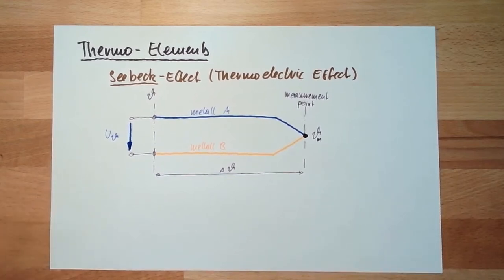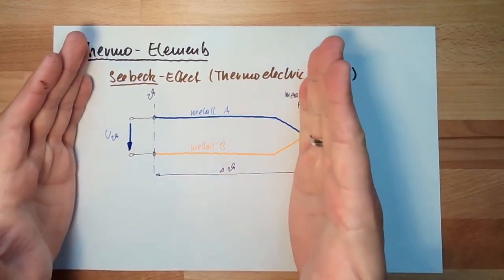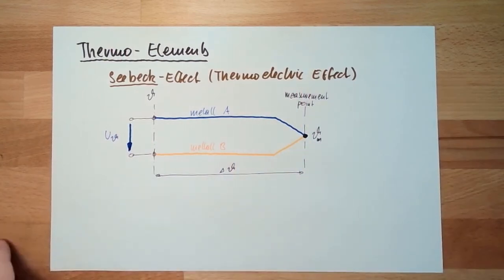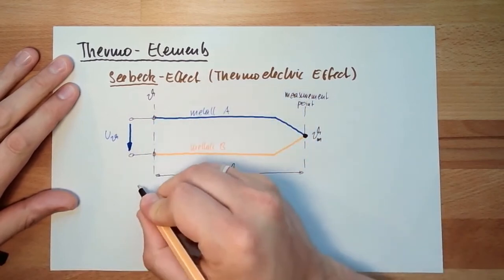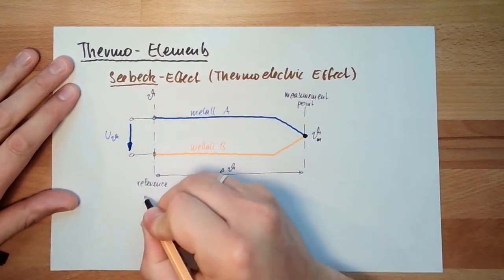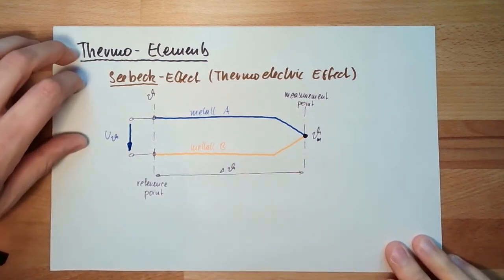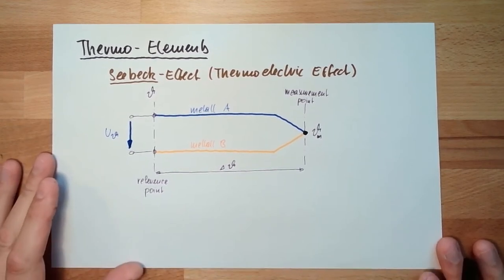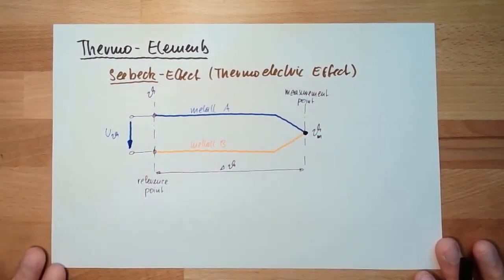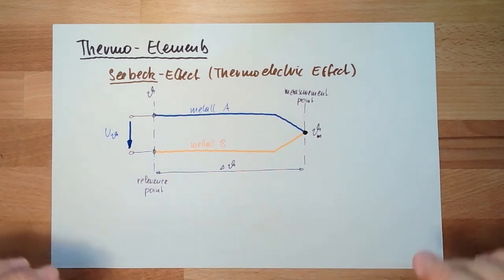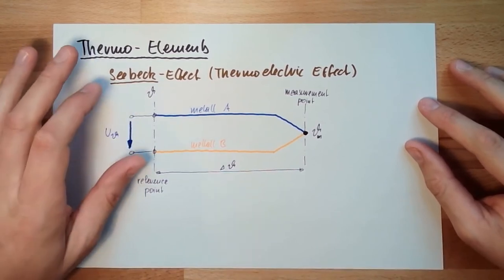It's not that easy, because it's not really reflecting the temperature. It's actually reflecting the temperature difference between the measurement point and the reference point. Here I call reference point. The delta temperature is reflected by this thermal voltage. This is the use of the Seebeck effect. I can only measure temperature differences between two points, and how big this difference is depends on the combination of metals I'm using.